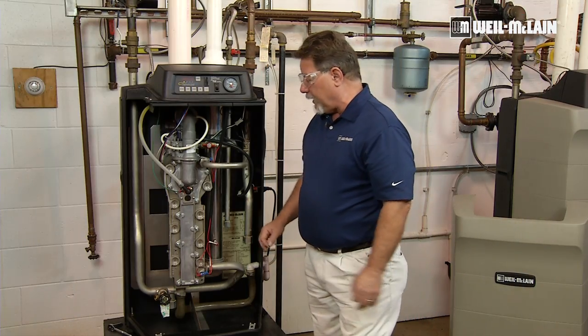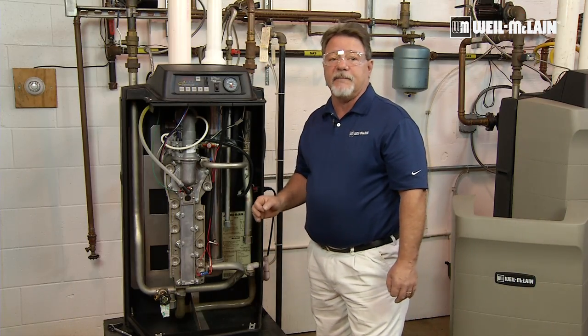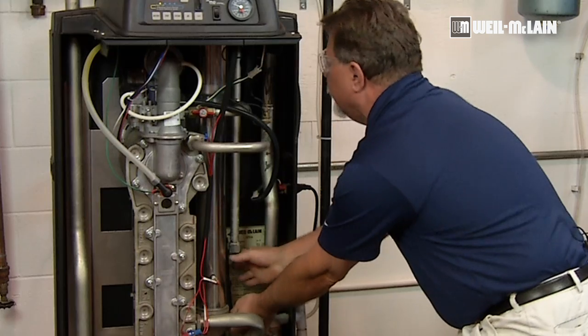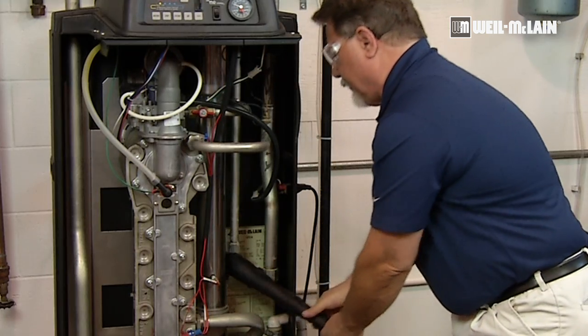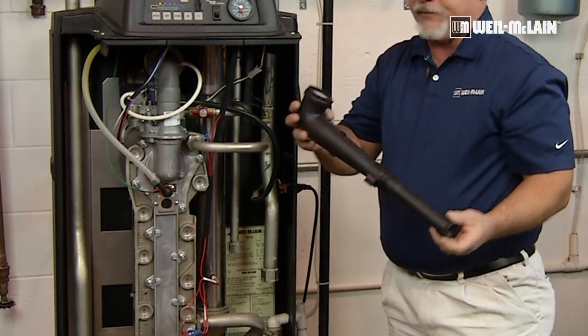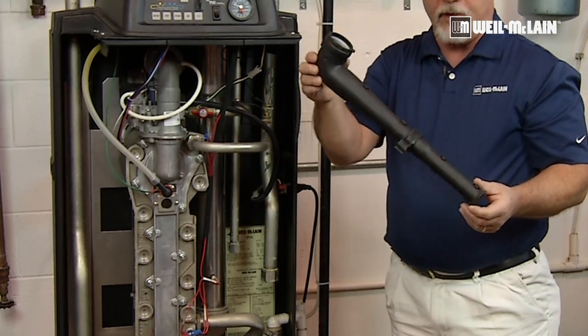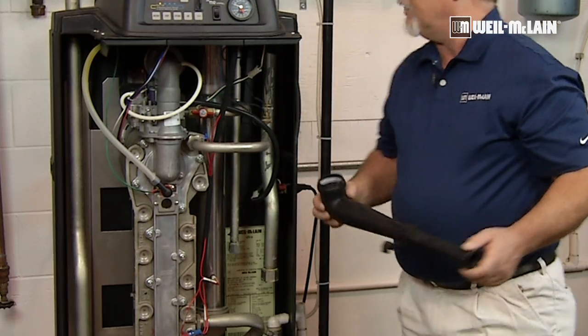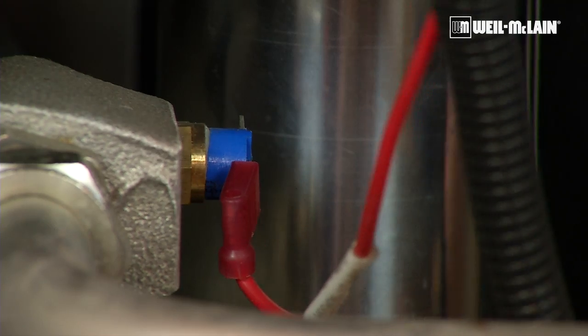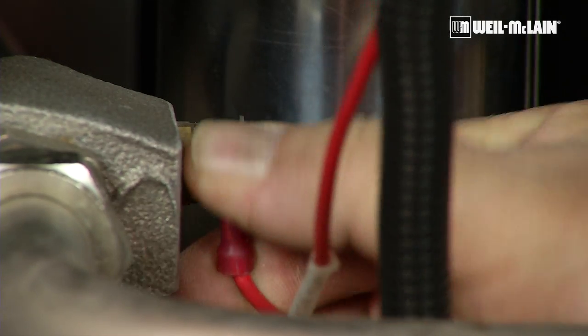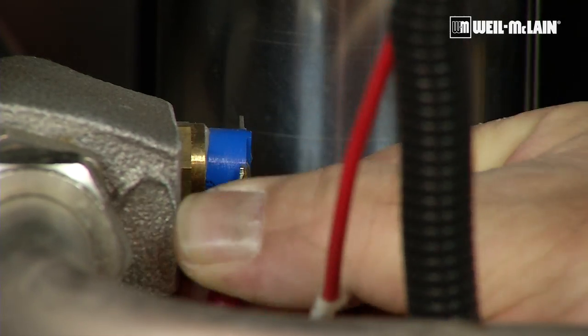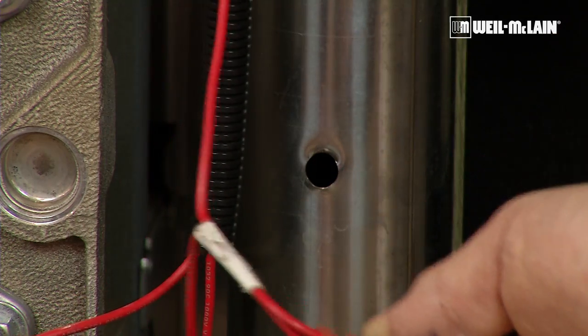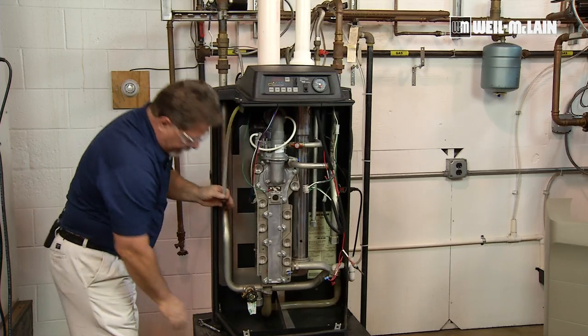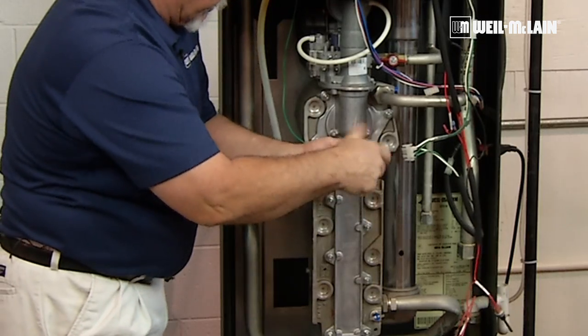So the first thing that we need to do is remove the silencer. So you simply remove the silencer from the adapter that connects it to the blower, and we'll set that aside. The next thing we really want to do is remove the wiring connecting the control module to the different components in the boiler. I'm going to remove the ignition cable, and I'm going to remove our ground cable.